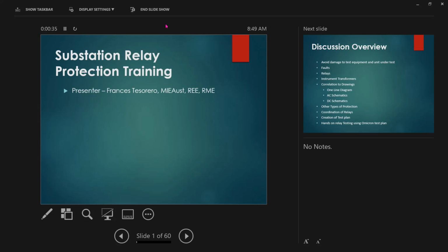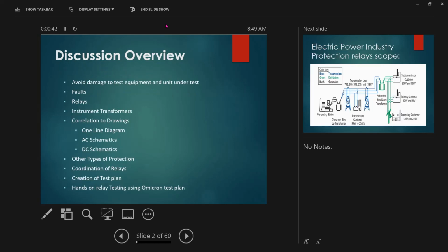So yeah, this training is not my initiative, but the initiative of Michael as our new manager. So he wants everybody to be aware. Like in our group anyway, if you are in breaker, most of the people just focus on breaker. If you do some transformer, you focus on transformer. But on relays, everything is connected. The relay makes the breaker do its job, trip it, and also it protects the cable and everything. So we can see how all of these services that we provide are interconnected to each other. So we'll give you a bigger picture.